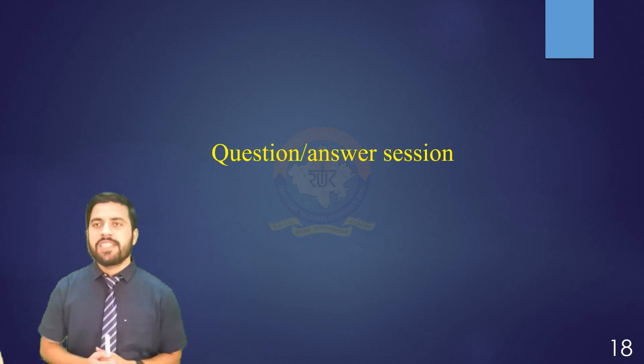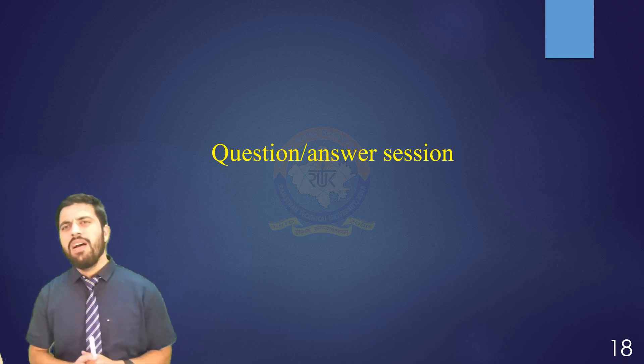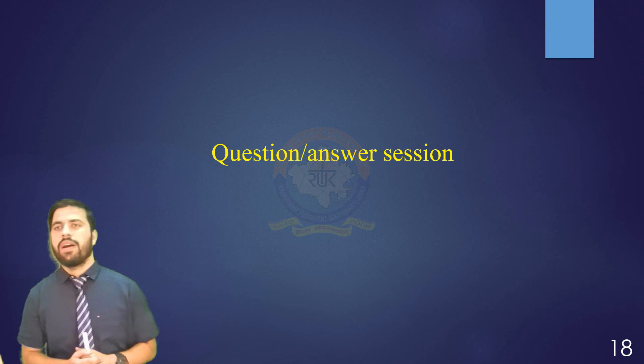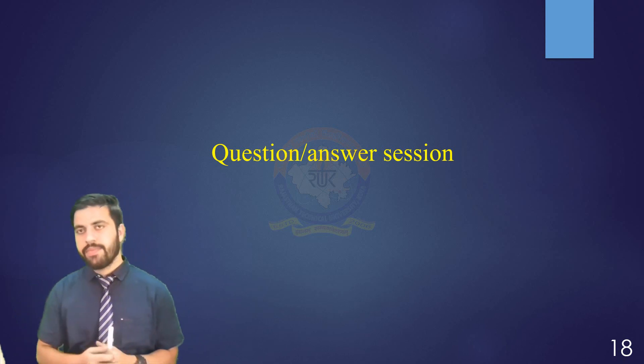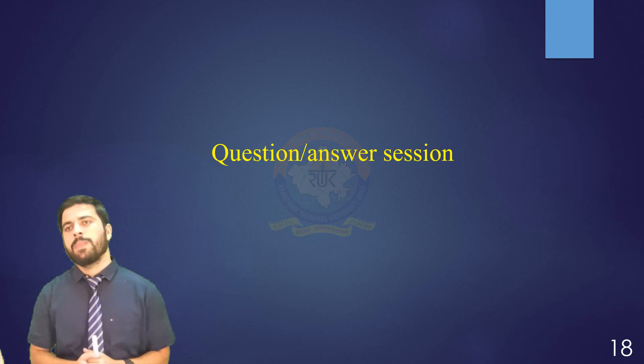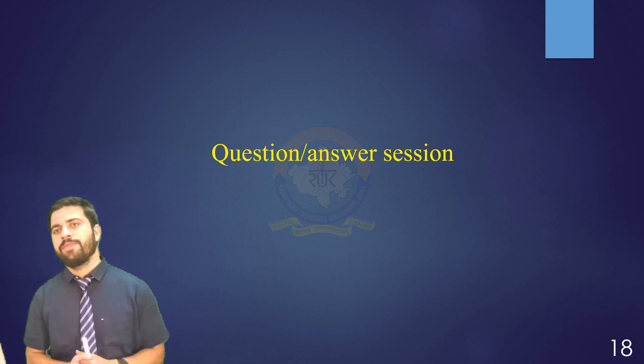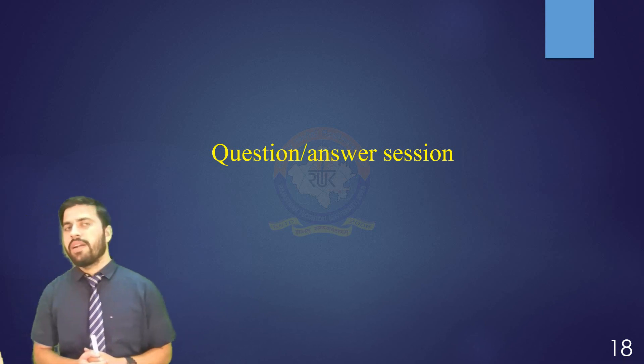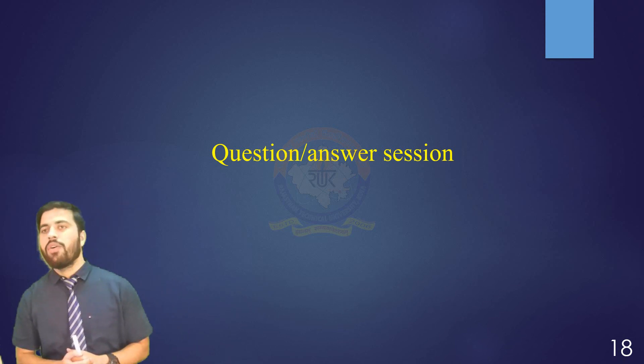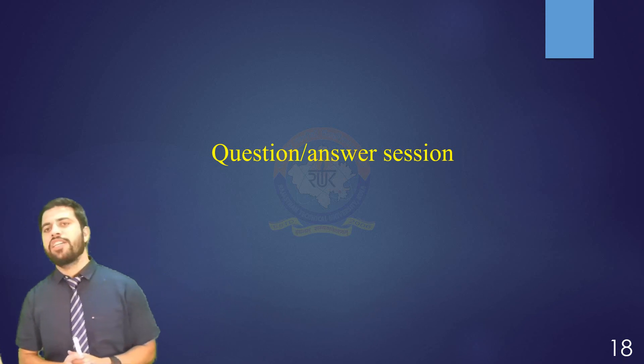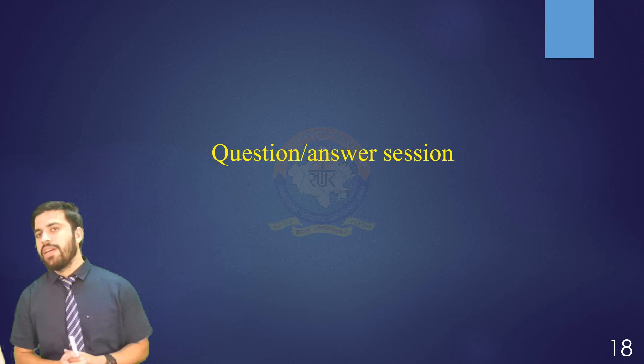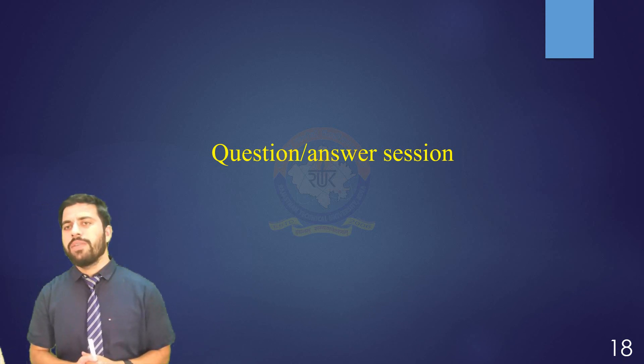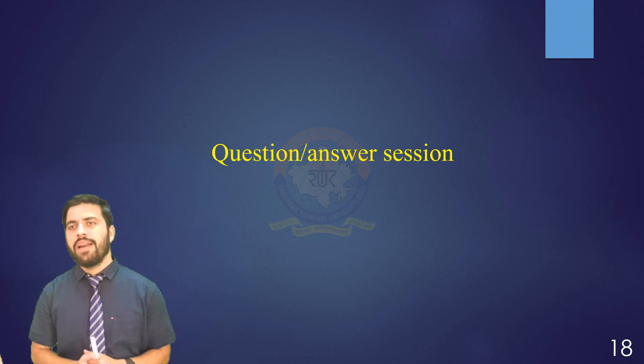Now coming to the question and answer session. Is anybody having an inquiry or doubt regarding the topic I have discussed today? One question: what can be done to prevent seawater corrosion-related issues in seawater systems based on plate type heat exchangers? The best way to overcome corrosion difficulty in a seawater environment is by using materials which are less susceptible to corrosion, such as titanium and copper alloys. Since the heat exchanger is plate type, coating is a good approach. Methods for addressing seawater corrosion include organic coating, cathodic protection, inhibitor treatments, and metallic coatings.